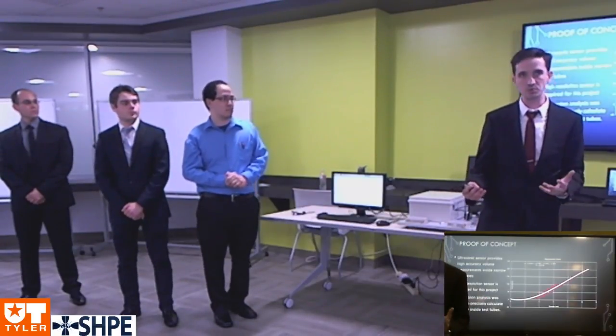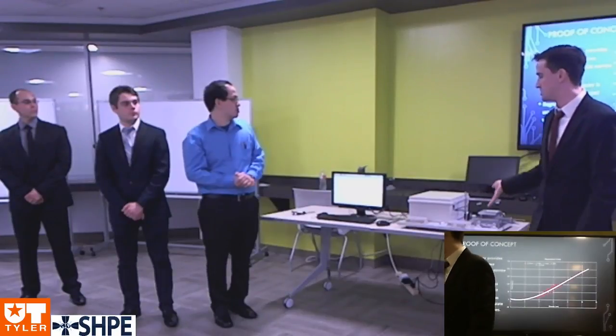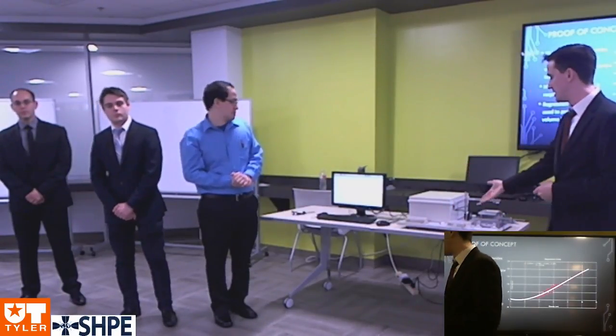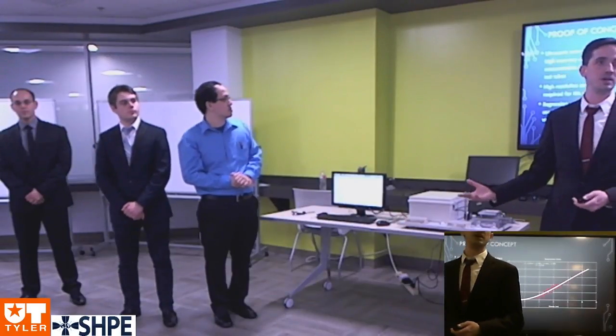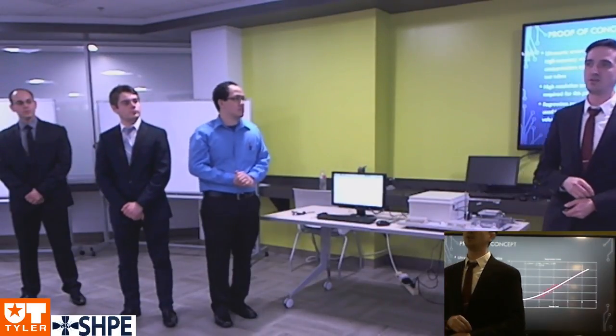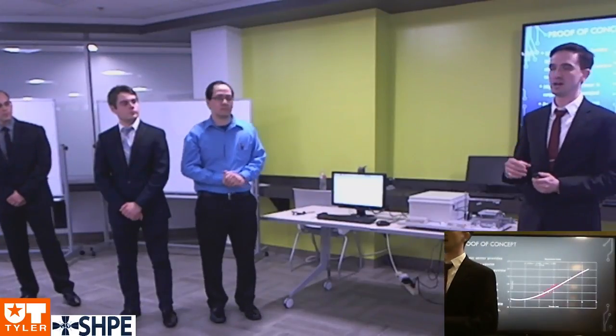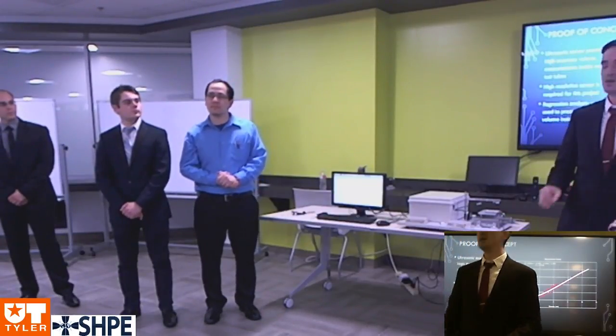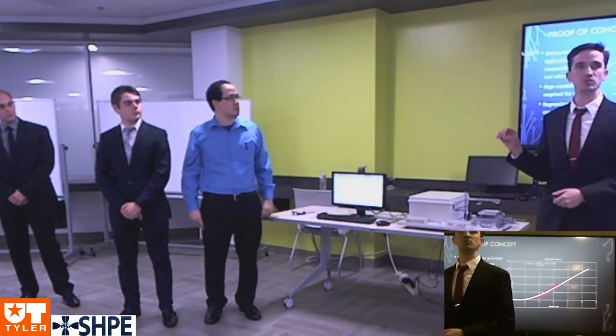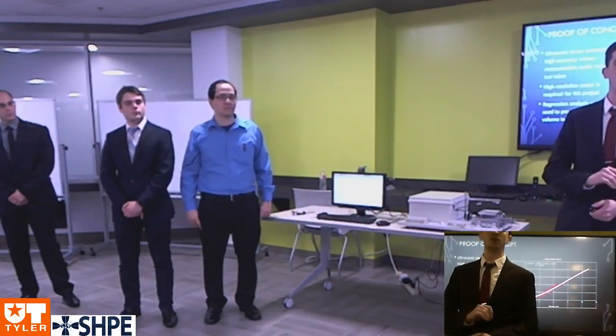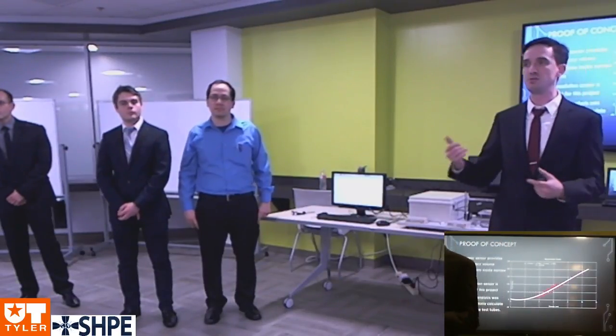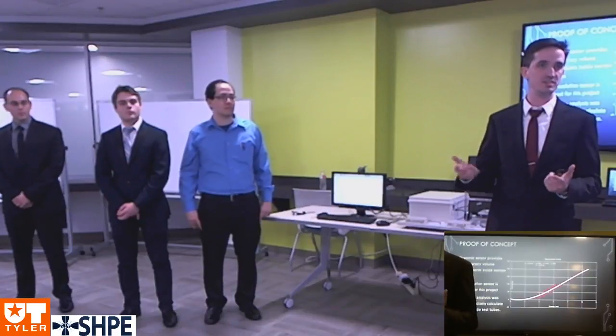And then what we did was we consistently would fill up the tubes with various volumes from the pipette. We would pipette it into the system, and then we would measure them. And actually what we found out was, and maybe it's just because in my lab we haven't calibrated our pipettes in a while, but the system that we developed was actually usually closer to the actual volume than the pipette was measuring. So I would measure 45 and I would get 46 in the weight.